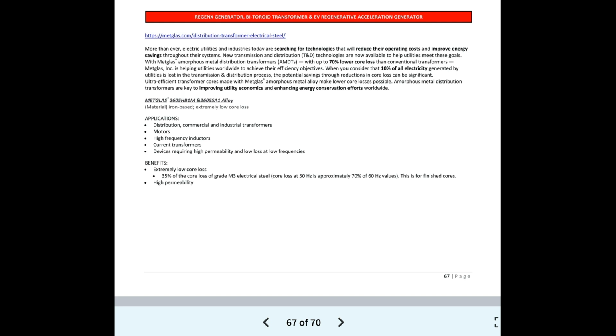METGLAS 2605SA1 and 2605HB1M alloy. Material: iron-based, extremely low core loss. Applications: distribution, commercial and industrial transformers, motors, high-frequency inductors, current transformers, devices requiring high permeability and low loss at low frequencies. Benefits: extremely low core loss, 35% of the core loss of grade M3 electrical steel. Core loss at 50 Hz is approximately 70% of 60 Hz values. This is for finished cores. High permeability.